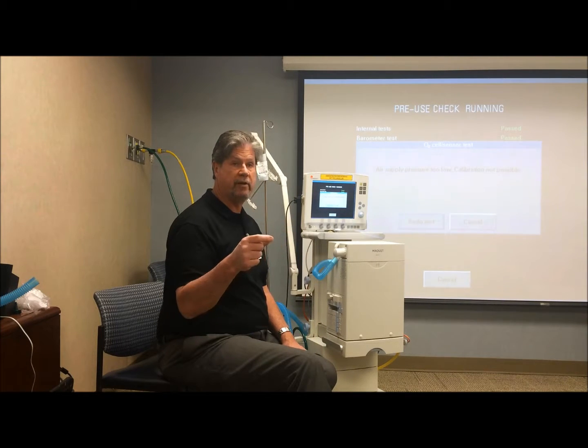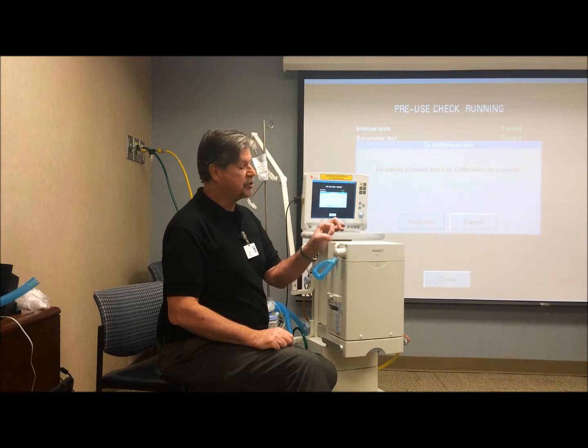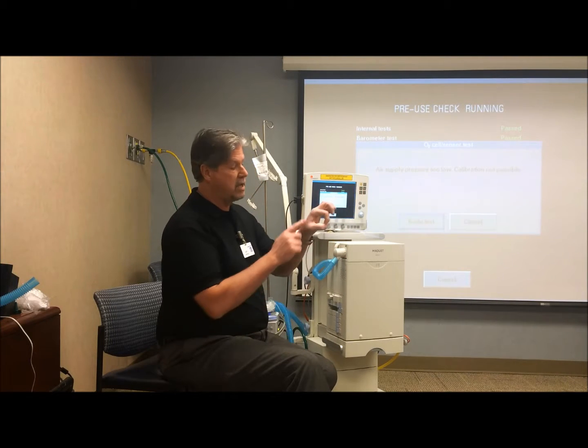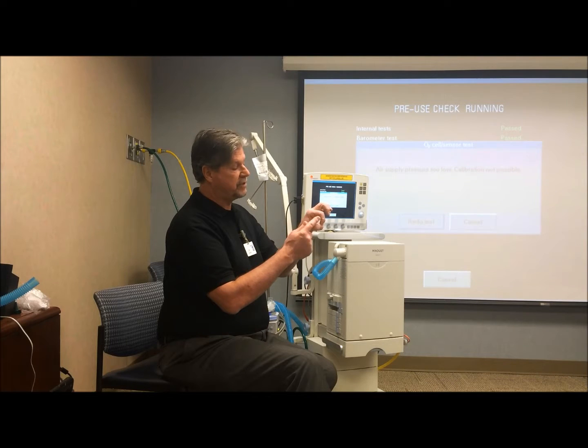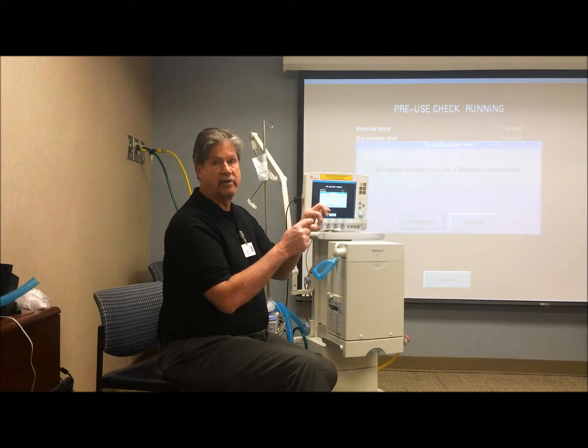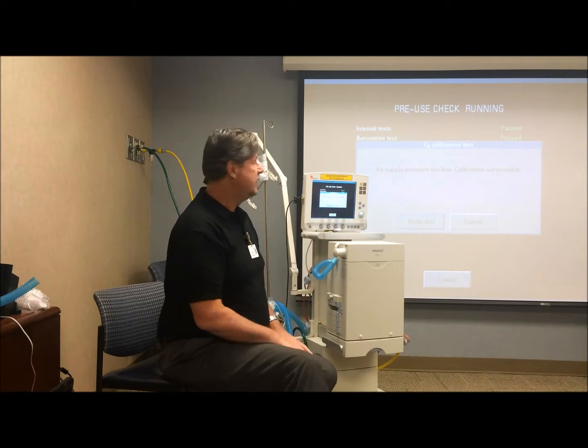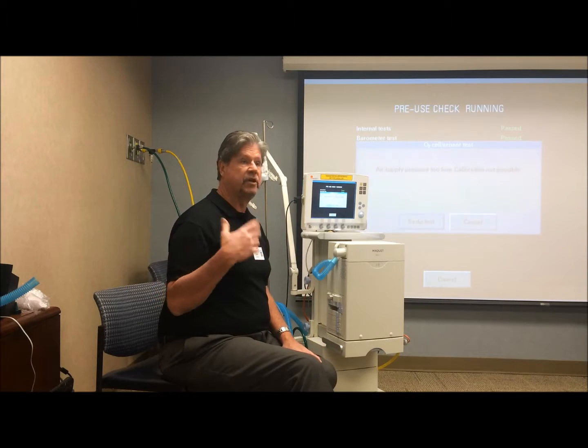If it still fails, I put the good one on the expiratory side, and I know that the expiratory side pressure transducer failed. The expiratory pressure transducer is a little circuit board about this big with a little teeny thing on it, and that's the pressure transducer. It's right on the circuit board. It's an electronic pressure transducer, but it still reads pressure.